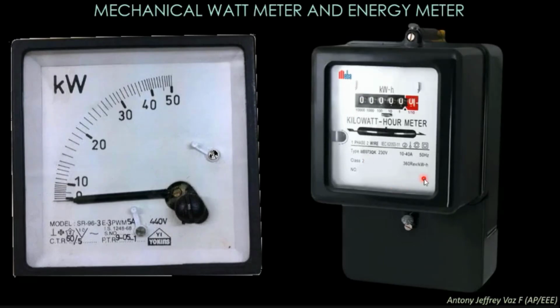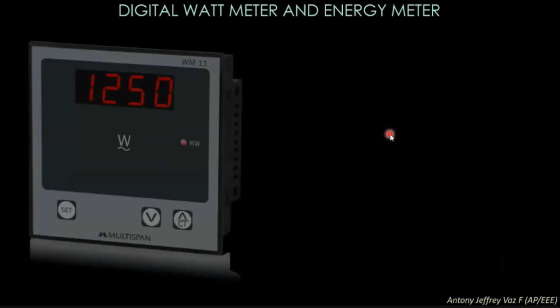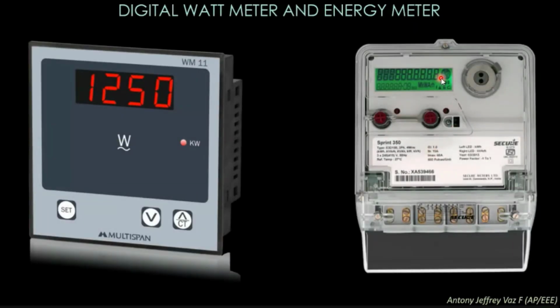Since this complete system works on a magnetic setup, if you keep a strong magnet outside the meter, the disk rotation will be stopped and there will be a loss for the energy producer, for example TNEB. To avoid this, they have changed to the digital energy meter. Here the measurement is made through a digital ammeter and digital voltmeter. There is no role for the magnetic field. So if you place a magnet near the digital energy meter, it will not affect it and the readings will be very accurate.